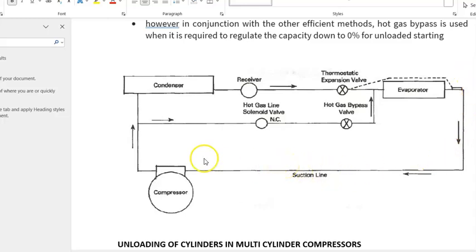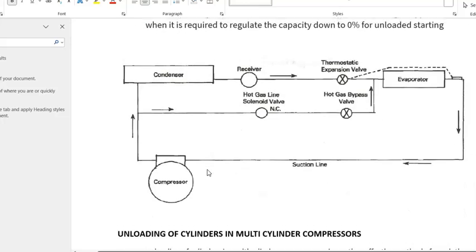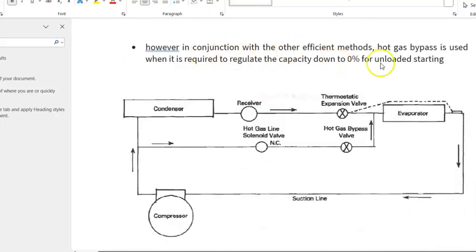This method is normally used for cleaning the evaporator by removing the oil, or sometimes you can use it as capacity control to maintain the temperature. The compressor normally goes to the condenser, receiver, then the thermostatic expansion valve, then the evaporator. This method bypasses through the hot gas bypass valve to the evaporator and suction line. If you want evaporator capacity at 0% for unloaded start, then you can use this hot gas bypass valve.